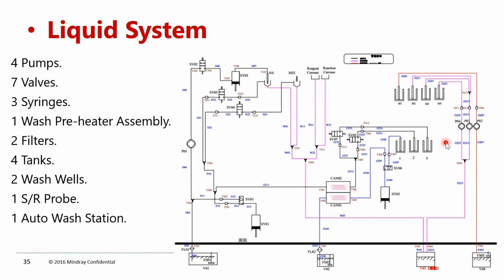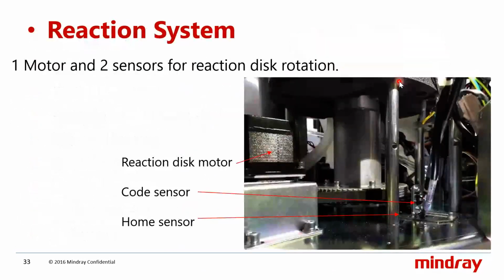It will compare with the previous reading, and simultaneously the light intensity of the previous reading. If the difference is much lesser, it means that there is a cuvette overflow. If the cuvette has any overflow, there will be a difference in the light intensity, and then it will trigger this alarm. Once that cuvette is validated, the cuvette will come back to the fourth probe. Here this wiper will empty the cuvette. Here there is no dispensing.